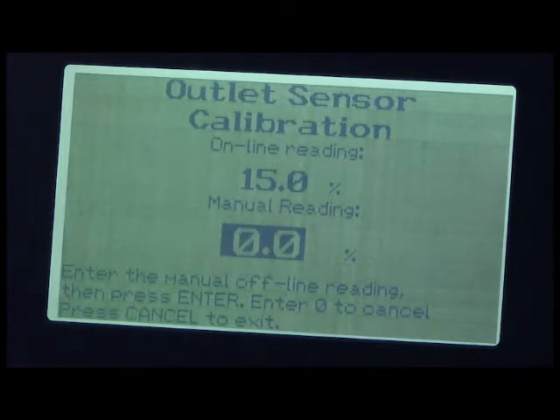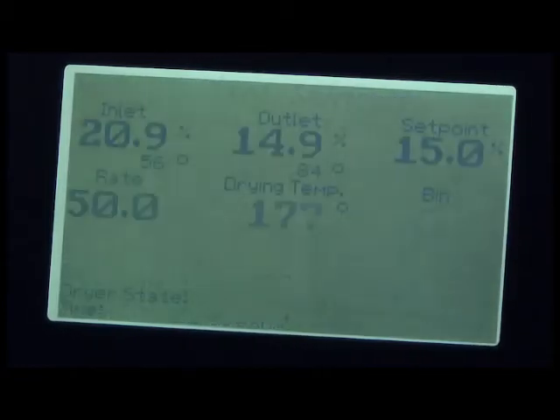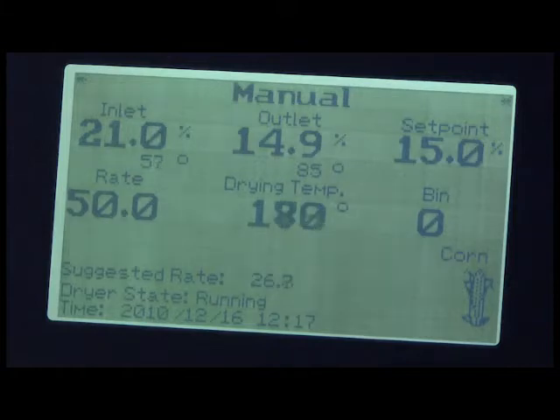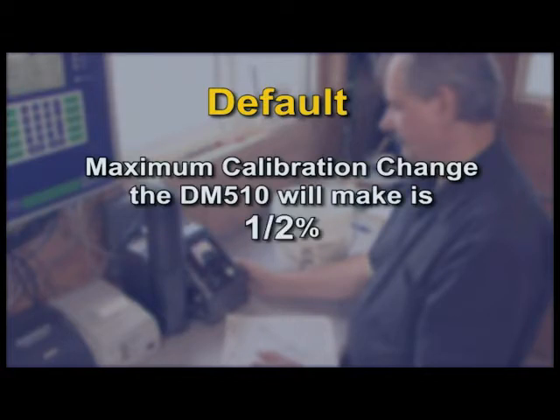H: Once selected, the moisture calculation will display. I: Enter your moisture value and press Enter. The Dryer Master will automatically update its moisture calculation formula. Note: by default, the maximum calibration change the Dryer Master will make is 1/2%. This is to prevent erroneous key entries or occasional bad samples from disrupting the operation. In practice, errors should be less than 1% on average. There may be instances where readings are significantly in error requiring more drastic steps — significant changes in product quality or start-ups are the most likely causes.